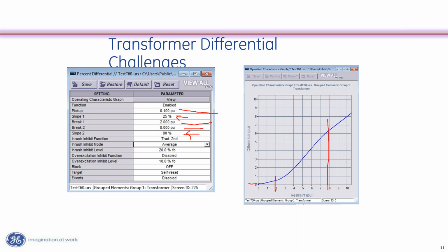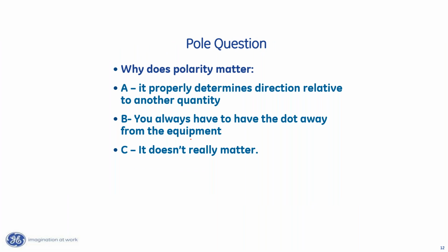So in other words, if I had 2 currents, the compensated currents on either side of the transformer, one of them was 1 per unit, the other one was 0.75 per unit. The vector sum of those, assuming that the 0.75 is at 180 degrees to the other one, would be 0.25. So my differential would be 0.25 and I'd operate. Now I'll talk about some guidelines for setting those a little bit later.